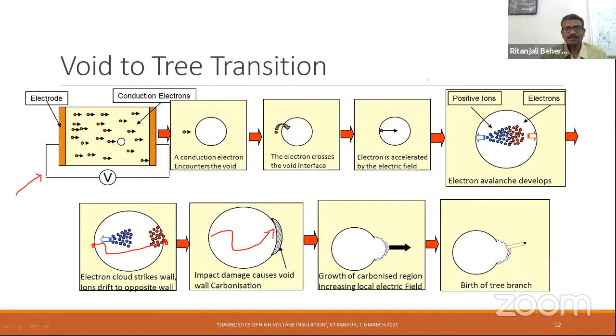And when the voltage goes up, this process repeats. So it is a repetitive process. In the process, this continuous impact of the discharge damages the void walls by carbonizing them, and this further carbonizes and leads to a first tree branch. This is how the first tree branch forms from the void, assisted by the partial discharge phenomenon.